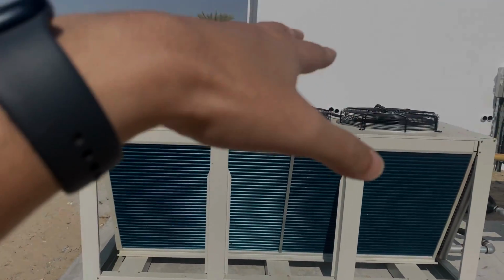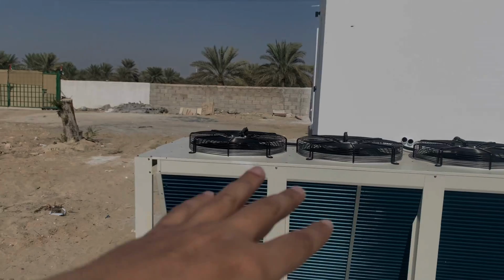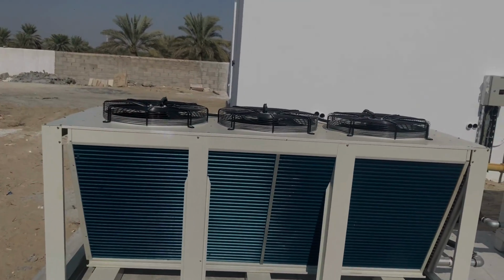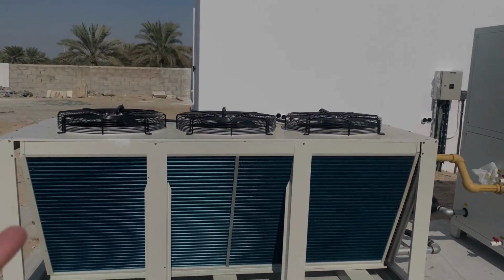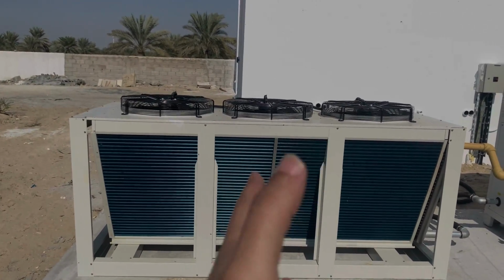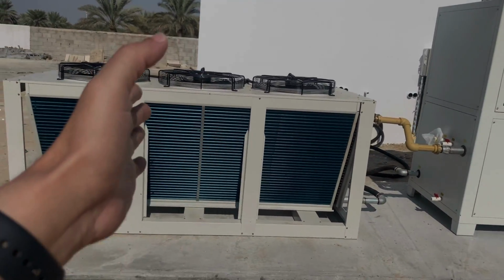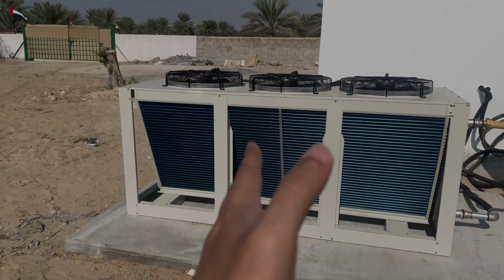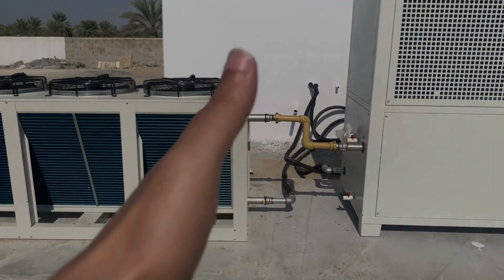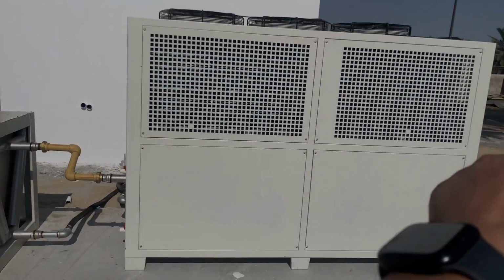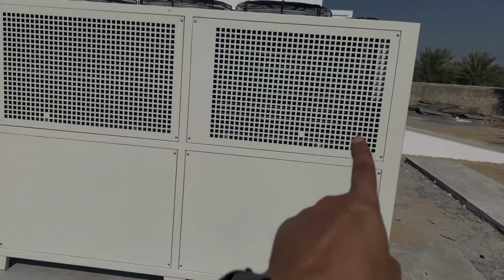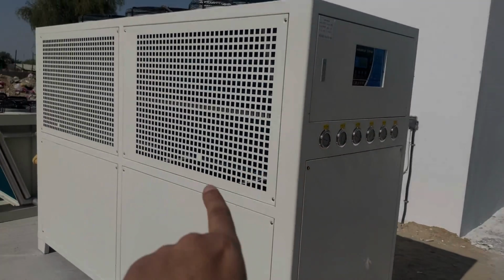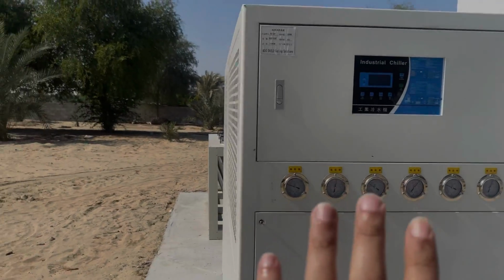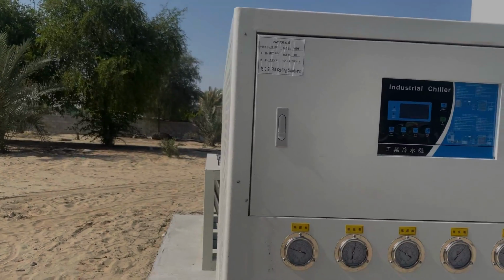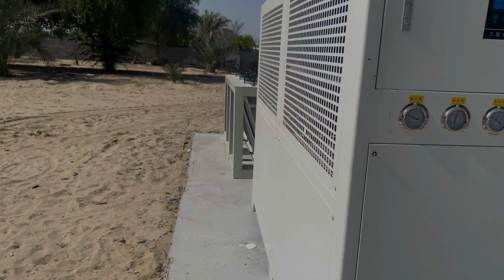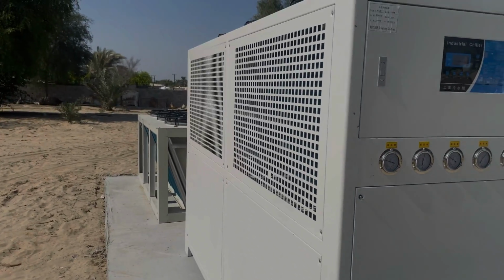The water will come out from the cabinets, from the miners, to the dry cooler first. The dry cooler will first try to get the temperature down to the target temperature set by Bitmain, which is 30 to 35 degrees Celsius. If the temperature is low enough within the target, which we can set here on the panel on the chiller, then the chiller will stay off, the compressors will not kick in. So we have only the water pump working inside, recirculating the whole fluid.